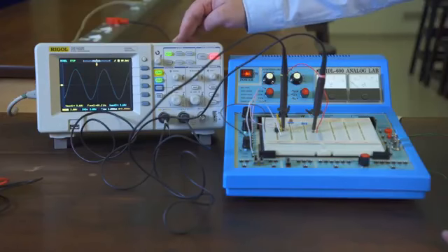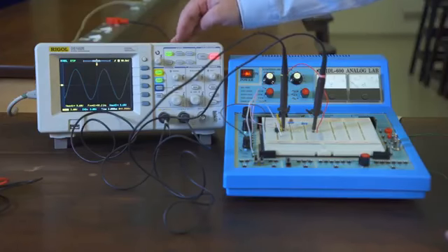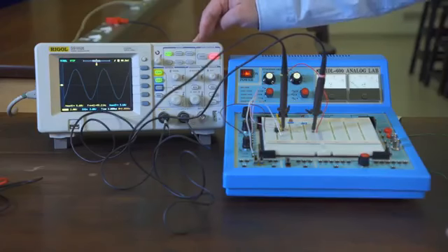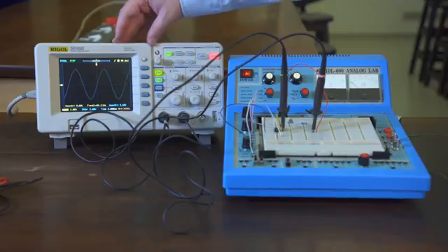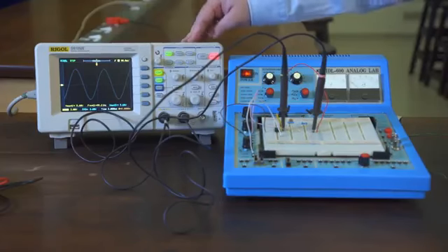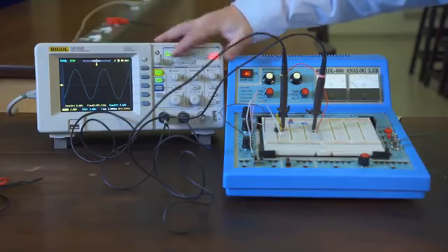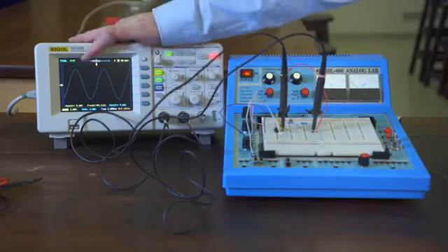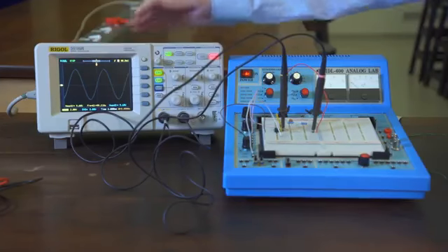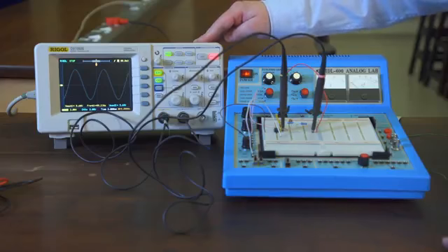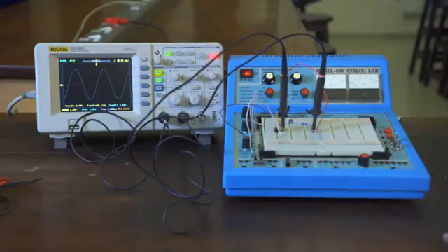Then we go to the increasing side of 3 times the 3 decibel, 6 times, 9 times, 12 times. Now for those intermediate ones of 1/12th to 12 times, all you're going to need to do is record your 3 values at the bottom of the screen and use your cursor function to find the time difference. And now if we go to our maximum value of 15 times, which is roughly, I think, 18 kilohertz.